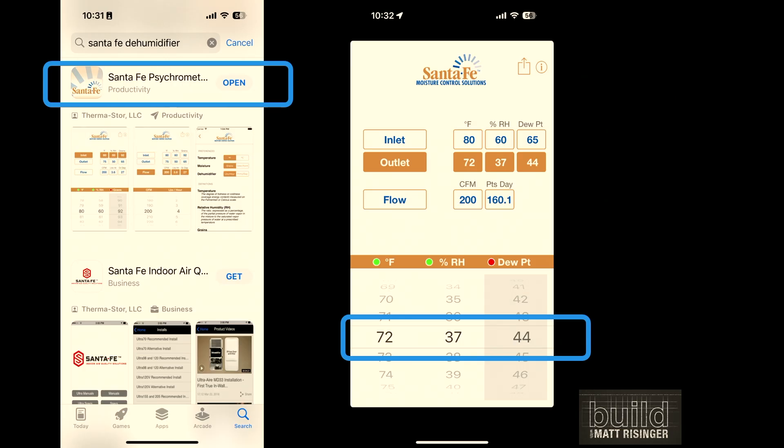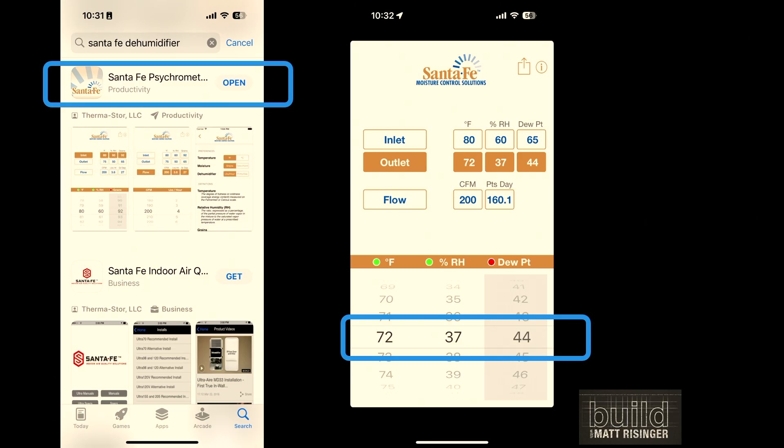What we need to figure out is what's the dew point at those indoor conditions to determine if condensation will occur. Santa Fe makes a free psychrometric chart app you can download from the App Store. At 72 degrees and 37% relative humidity, the dew point — the temperature at which dew will form — is anything 44 degrees or lower. Like an iced tea glass on a summer day sweating on the outside, that's exactly what's happening on those windows.